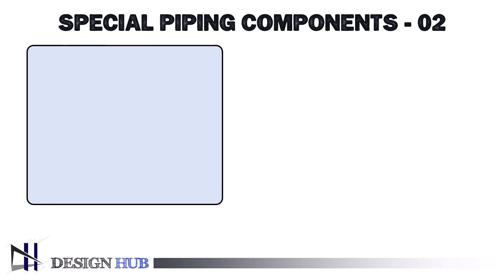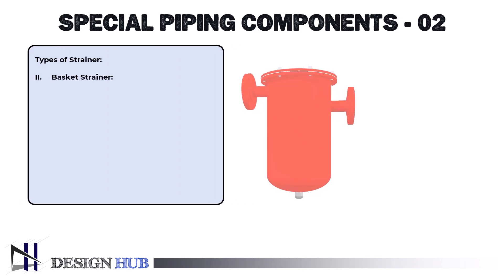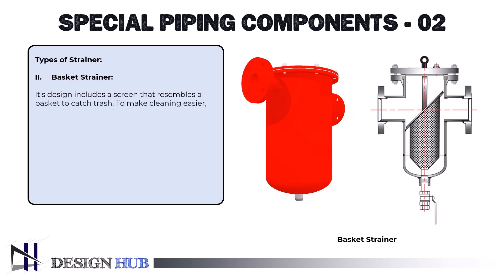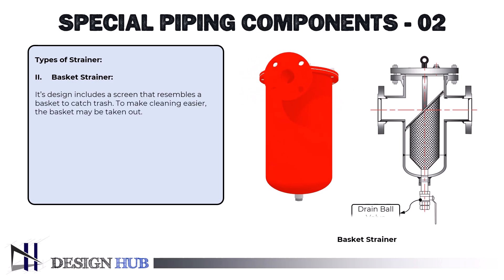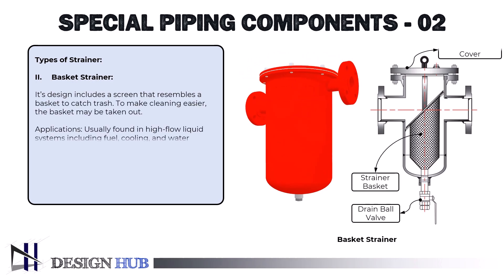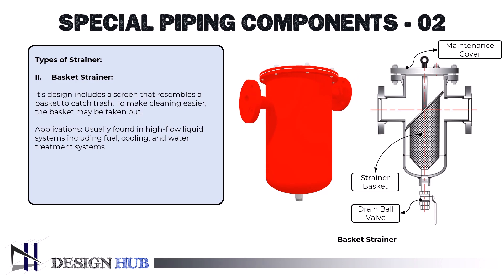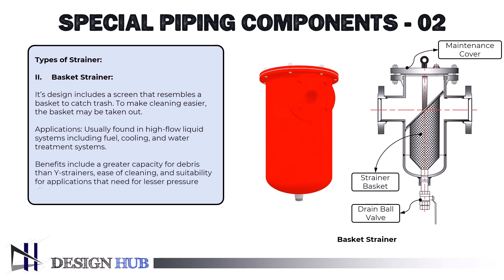The second one is the basket strainer. Its design includes a screen that resembles a basket to catch trash. To make cleaning easier, the basket may be taken out. Applications: usually found in high-flow liquid systems including fuel, cooling, and water treatment systems. Benefits include a greater capacity for debris than Y strainers, ease of cleaning, and suitability for applications requiring lesser pressure drops.